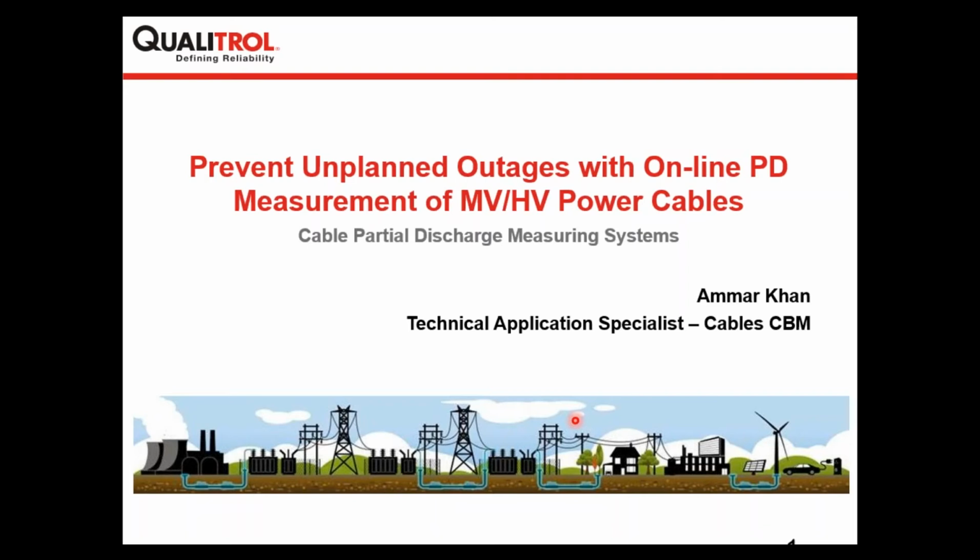So cable partial discharge is a different platform, and as you can see it has a different technology and a totally different amount of data which we are getting from the power cables. That's why we have kept it as a separate platform till now, but it can be integrated into the same server. So if you have an existing GIS transformer PD monitoring solution from Qualitrol, you can integrate the same system for partial discharges in the power cable.